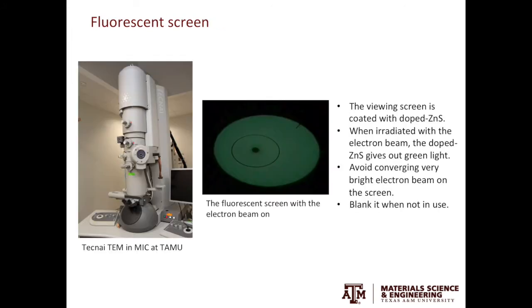On the left is a photograph of the TEM in MIC at Texas A&M University, and the fishbowl-shaped chamber is the viewing chamber. If you remove the blank and turn on the beam, you can see the illumination, and the light is green. The screen is coated with doped zinc sulfide, and when zinc sulfide is irradiated with the electron beam, it will give off a green light which the human eyes can see.